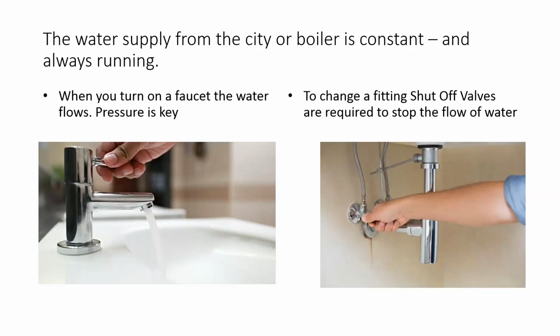A question that often gets asked of us is, what is a typical water pressure? What do you recommend? In our installation guidelines, we like to say that 40 to 60 psi, or pounds per square inch, is a good range and a highly operable range to work. Of course, you can have performance outside of those areas, but if you do have extremely high pressure, you may want to consider a pressure reducing system that your plumber can install so that you don't possibly blow out valves or joints or piping because of too much pressure. Or on the opposite end, if you have too low of pressure, you may want to consider a pressure booster so that that pressure can really get to an optimal performance area for the client.